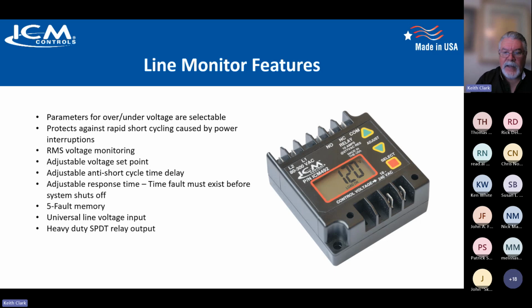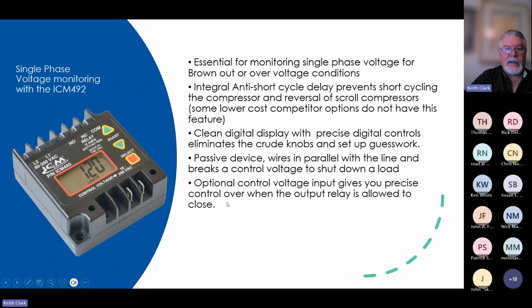So it's 80 to 300 VAC, heavy duty single pole, double throw relay output if necessary. And the thing that's kind of nice about these from a competitive standpoint, they're essential for monitoring that brownout condition or those overvoltage conditions, continuous overvoltage condition, not a spike, but that continuous overvoltage condition, which can fry windings in the motors and stuff. Short cycle delay is important to prevent short cycling. And then some of the competitor models don't have that feature. Clean digital display, precise digital controls. And some might have potentiometer type knobs on there or something, which are not very accurate. These are dead nuts accurate. Programming eliminates any guesswork. And it's a passive device, so it wires in parallel with the line and breaks a control voltage to shut down a load.